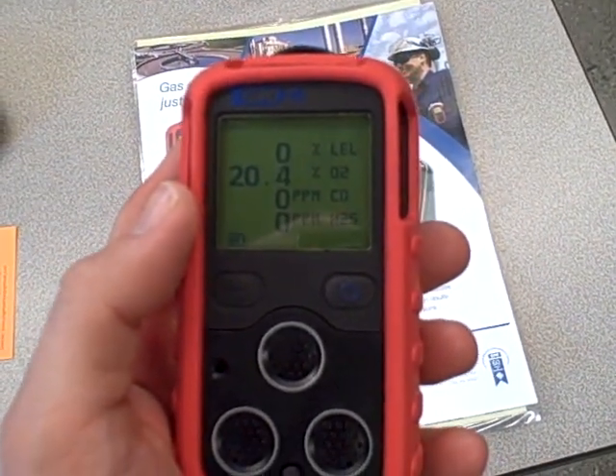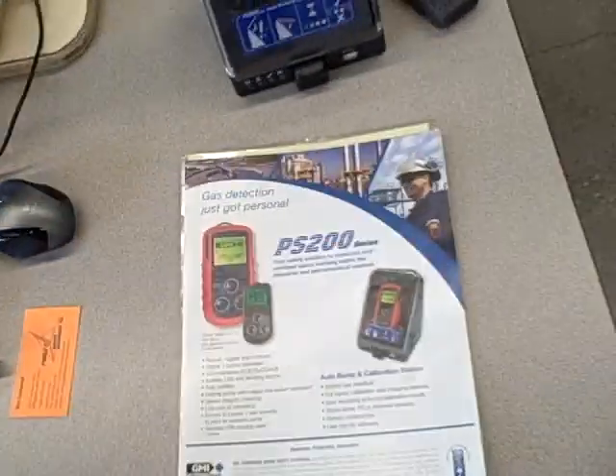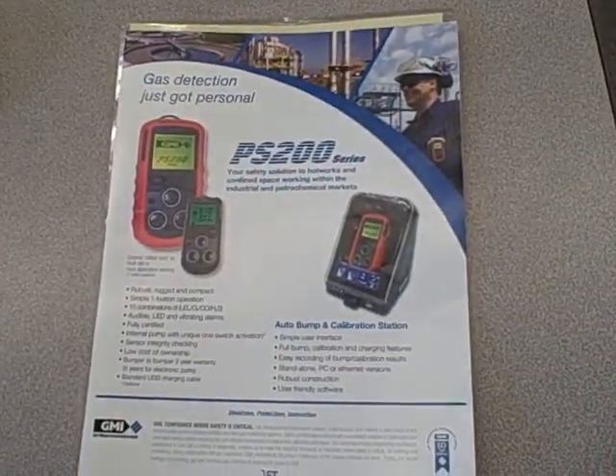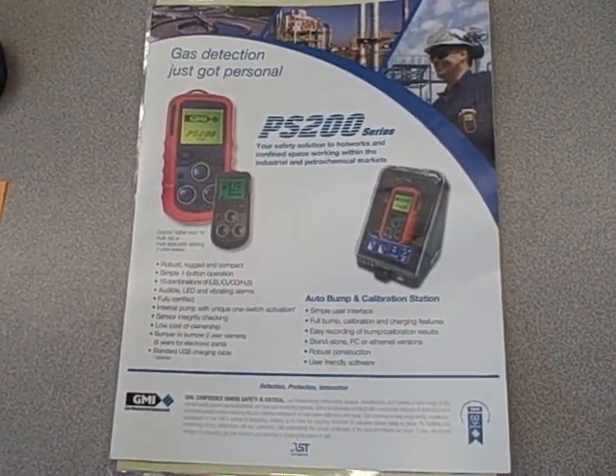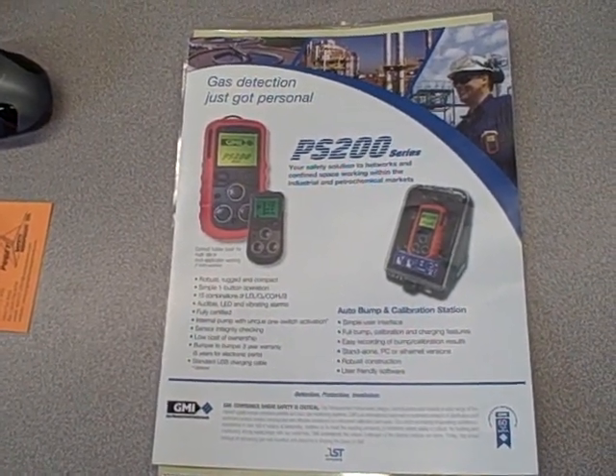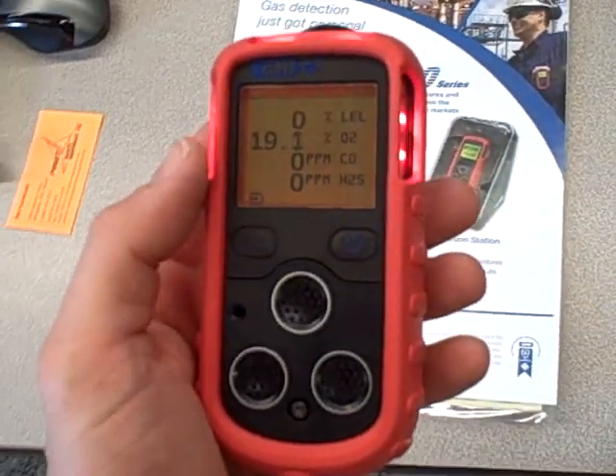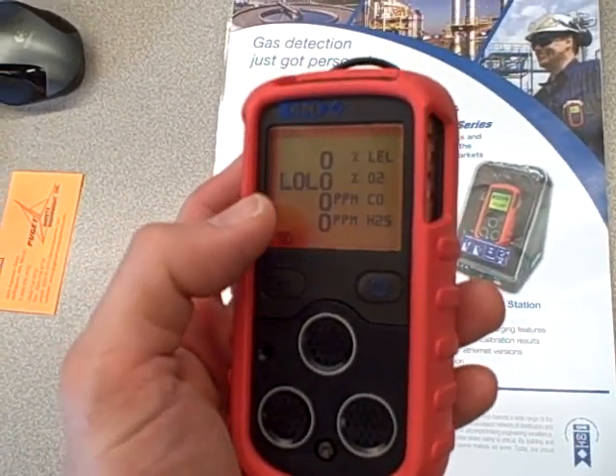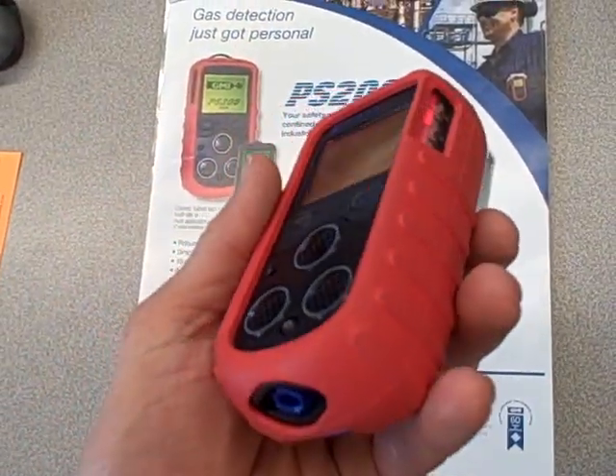See if that was enough. I hit a new low, but not enough for an alarm. Let me try this again. There we go — you hit the lower limit. Nineteen point five percent oxygen. And of course it's flashing and making a really annoying beeping sound.